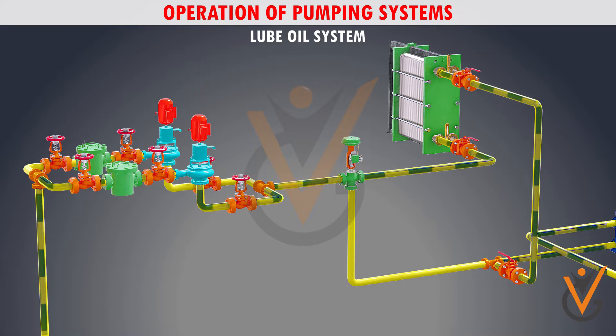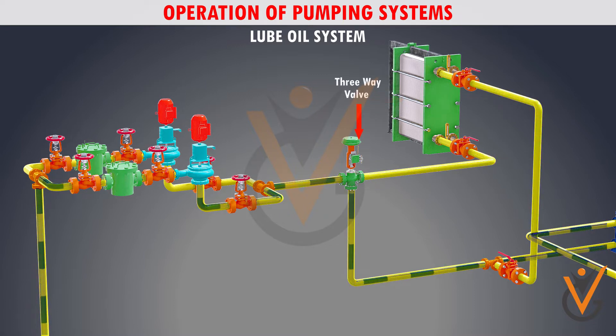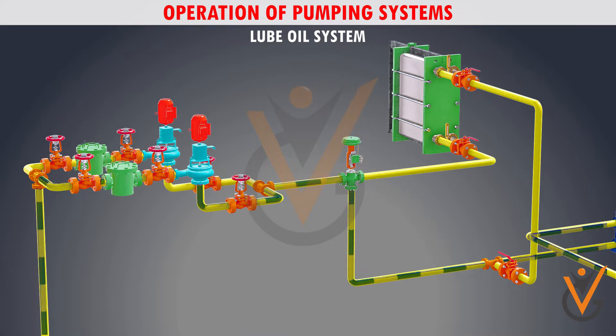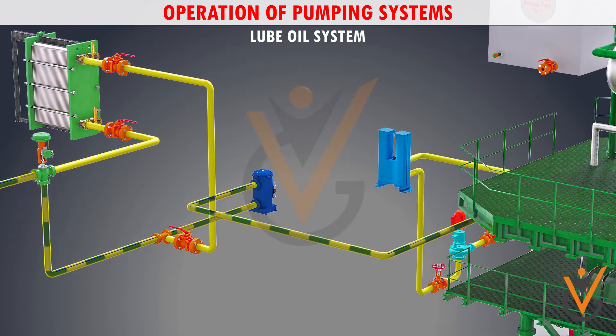The plate type or shell and tube type lube oil cooler is cooled from the low temperature central cooling freshwater system. The lube oil supplied to the cooler is via a three-way valve which enables some oil to bypass the cooler. This helps the three-way valve maintain a temperature of around 45 degrees centigrade at the lubricating oil inlet to the engine.